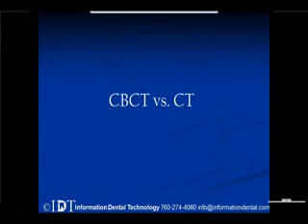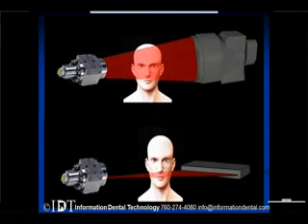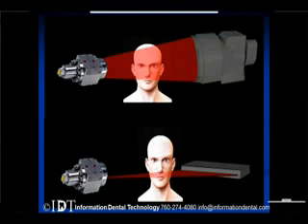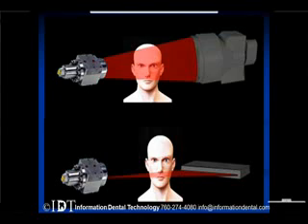A common question is: what's the difference between cone beam and medical CT scans? In the cone beam, the beam covers an entire area — for example, a 9-inch scan of the temporomandibular joints — in just one shot. The medical CT uses a fan beam instead, which covers a very small area. The fan beam rotates upward slightly, overlapping the lower beam and taking another image repeatedly until it completes the full 9-inch view, then those images are stitched together.